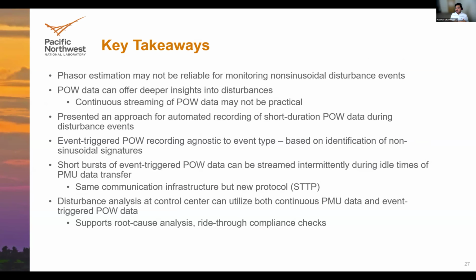The triggering condition is agnostic to the event type, but relies on identification based on non-sinusoidal signatures. So what we did was transport short bursts of event-triggered point on wave data intermittently during the idle times of PMU data transfer, utilizing the same communication infrastructure, but a different protocol. For the disturbance analysis at the control center, you can utilize both the existing continuous streams of PMU data, as well as the short duration event-triggered point on wave data. This can support root cause analysis and also help in checking for ride-through compliance.